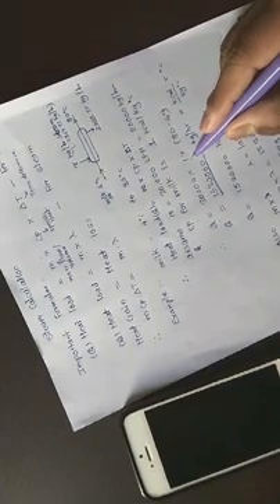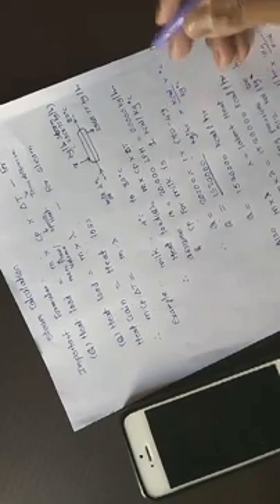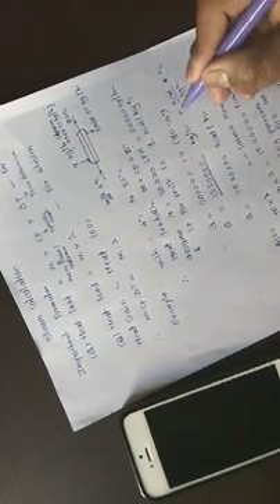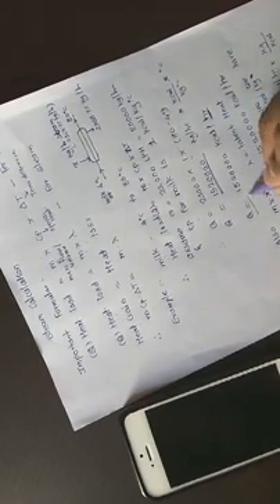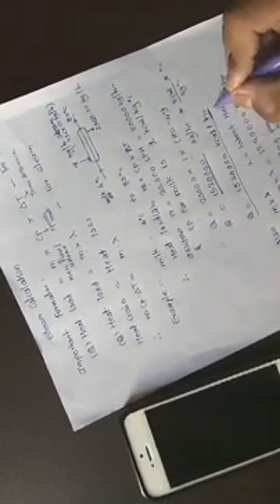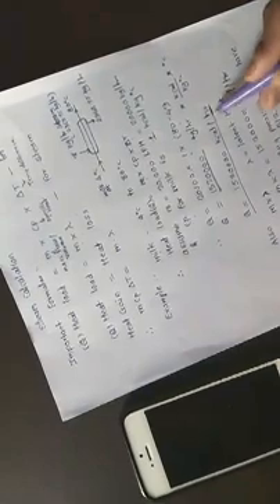What is kilocalories per kg degree Celsius? That is Cp, the specific heat of water or milk. Then what is delta T? That is 76, that is in degree Celsius. So I have calculated, and when you divide the units also, you will get kilocalories per hour. This is the heat load from the product side, which is per hour. You want to heat the particular product in 1 hour, because you have the flow rate per hour, then the steam calculation will happen in kg per hour.